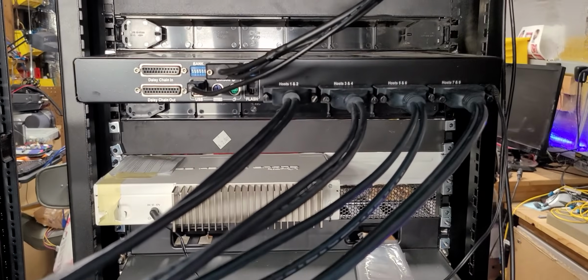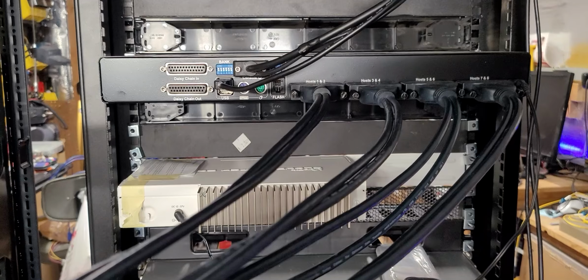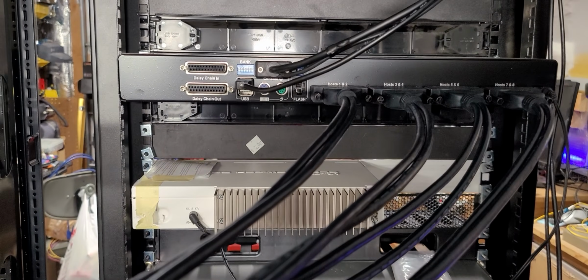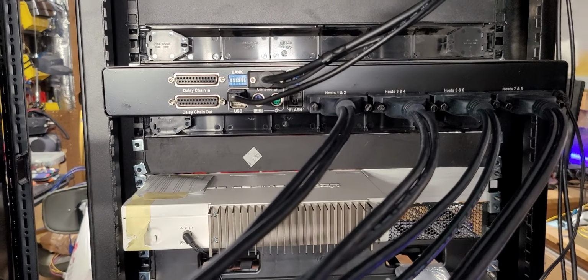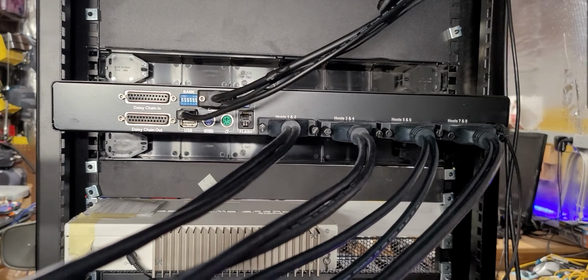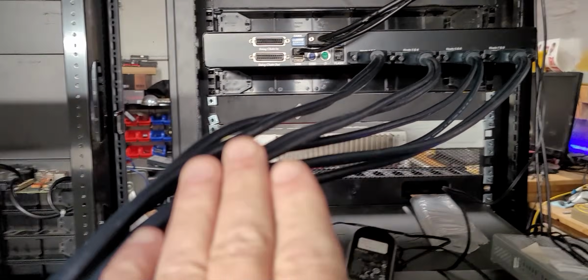By putting your KVM in first, before you put power and then your network LAN connectivity, and then lastly you put your most sensitive cables like GBICs and SAS connections and mini SAS connections and fiber optic cabling last, you want to section them off using your bridge. This is the bridge right here that takes the stress off the cables and allows everything to run fairly smoothly and keep good airflow in the area you're working with.